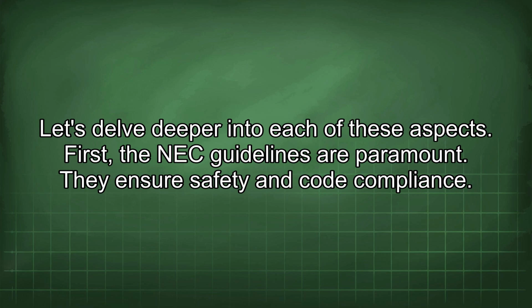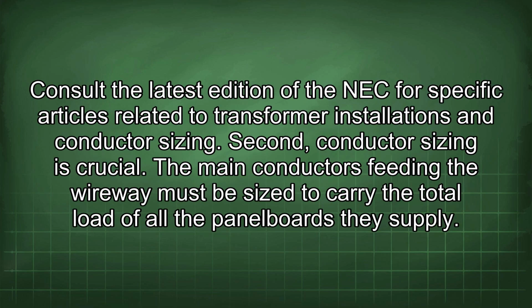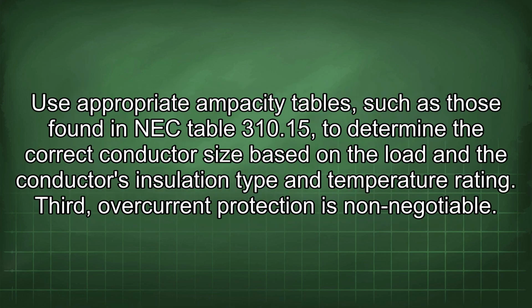Let's delve deeper into each of these aspects. First, the NEC guidelines are paramount. They ensure safety and code compliance. Consult the latest edition of the NEC for specific articles related to transformer installations and conductor sizing. Second, conductor sizing is crucial. The main conductors feeding the wireway must be sized to carry the total load of all the panel boards they supply. Use appropriate ampacity tables, such as those found in NEC Table 310.15, to determine the correct conductor size based on the load and the conductor's insulation type and temperature rating.